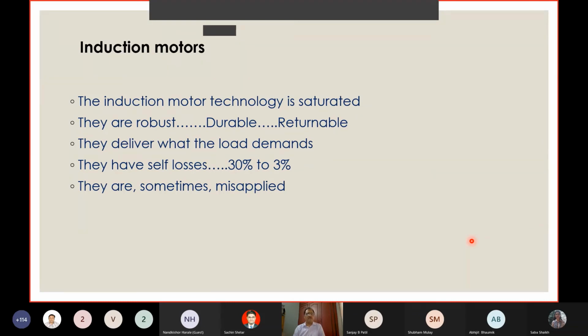Motors' whole-time job is to deliver what the load demands. They won't deliver all that they have. They will deliver only what is demanded from them by the load. And their own self-losses, as you saw in the first slide, 85 to 96% is the efficiency. Their own self-losses would be 30% to 3%. We can't reduce from 30 to 3, but we can always attempt reduction. When it comes to 30, 10% reduction is possible. When it is 3, approximately 1% reduction in losses is possible.